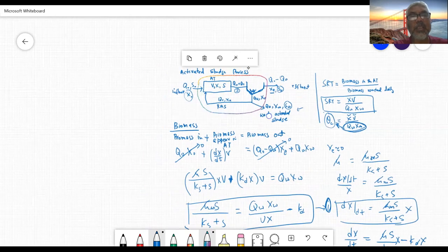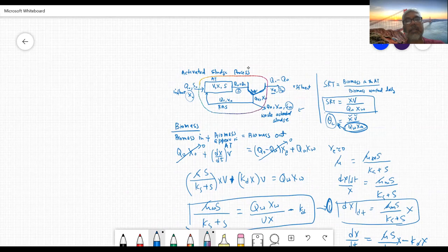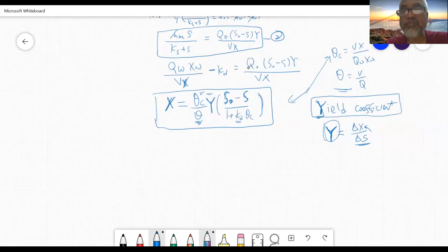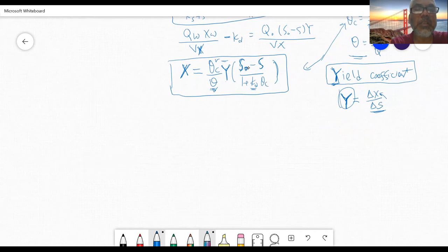You can compute the concentration of biomass in the aeration tank if you know certain constant values. If you fix theta c, the sludge retention time, and if you fix the hydraulic retention time, then Y is a constant and Kd is a constant. And if you know S naught, the influent concentration, and the concentration of substrate in the aeration tank, or in effluent, which is the same thing, then you can compute it.